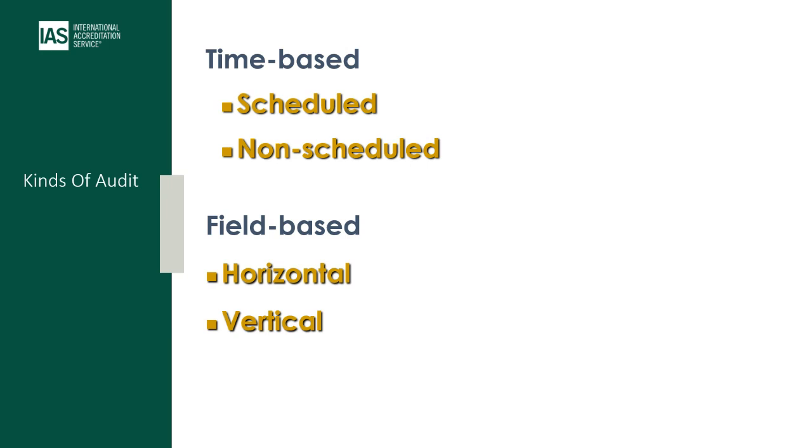Now, if there is an error or if there is a doubt, then you have to do a horizontal. So you picked up the instrument and you found that, oh, calibration not done here. Not good. All right. So then you go to another instrument and say, did you do your calibration? Show me your calibration records. You go to another instrument, do a calibration check. Now, if the calibrations are failing, then you will see that along the equipment line. So you've got to mix the vertical and horizontal as a means to capture the full picture.